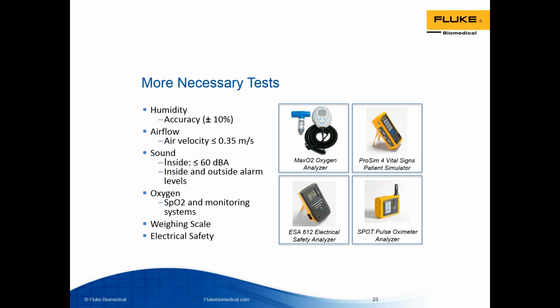So more necessary tests, talking about humidity. So check the accuracy of the relative humidity if your facility does use humidity at all in your incubators. And the humidity should be within plus or minus 10% of what the tester indicates. The air velocity inside the incubator compartment should be measured to make sure it's at or below that 0.35 meters per second that we talked about. Check the oxygen concentration, if it's used, to validate that it's within the acceptable range and that the visual and auditory alarms are appropriately activated. And along with providing oxygen-controlled environments, many incubators also contain built-in SpO2 and monitoring systems and are part of the testing and preventative maintenance for incubators. As we touched on earlier, a lot of incubators do double as weighing scales.